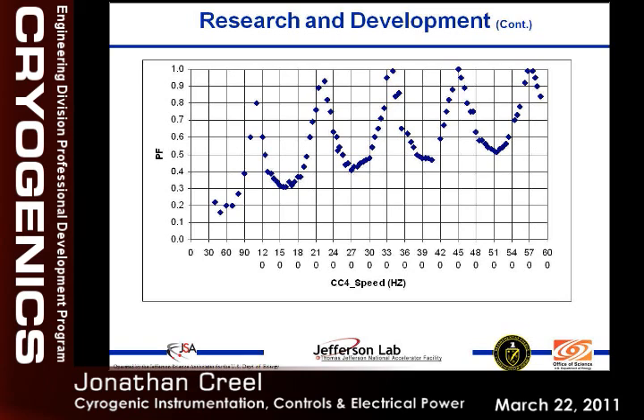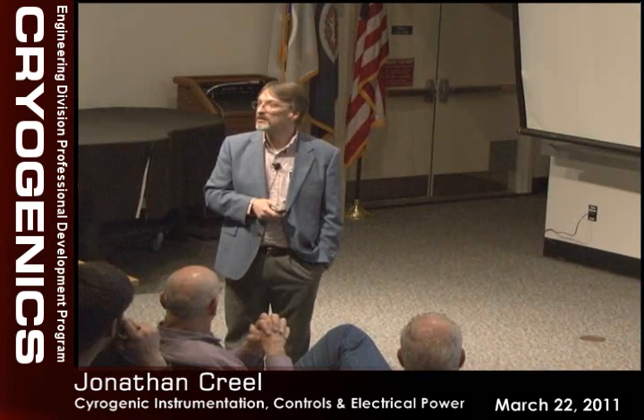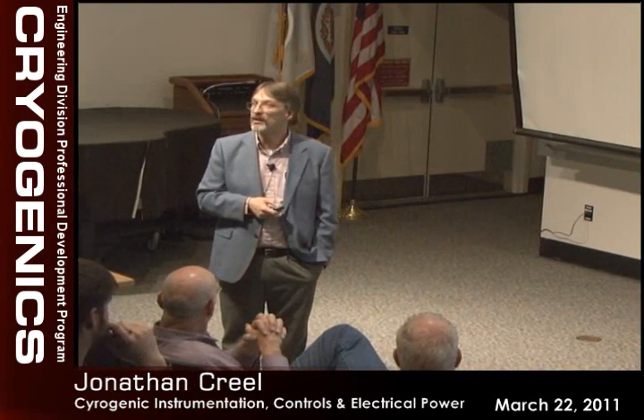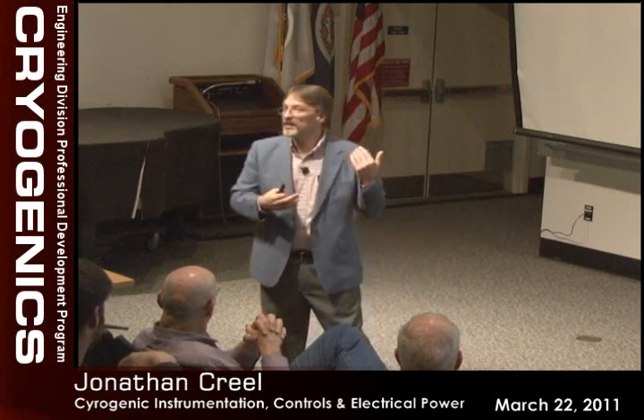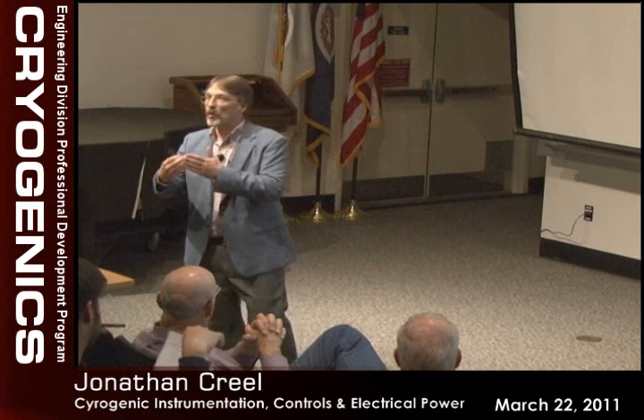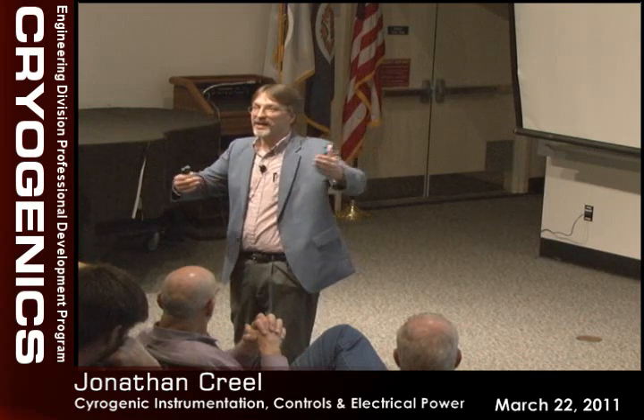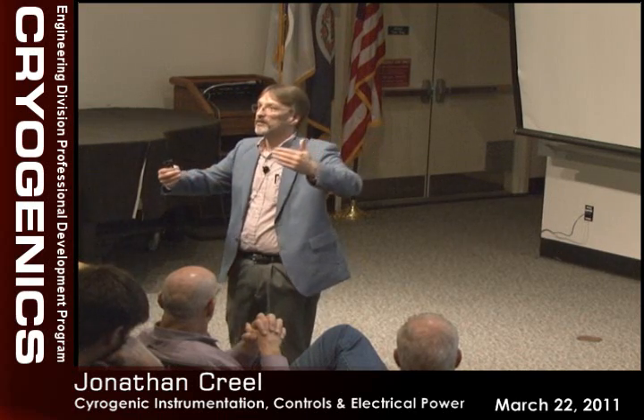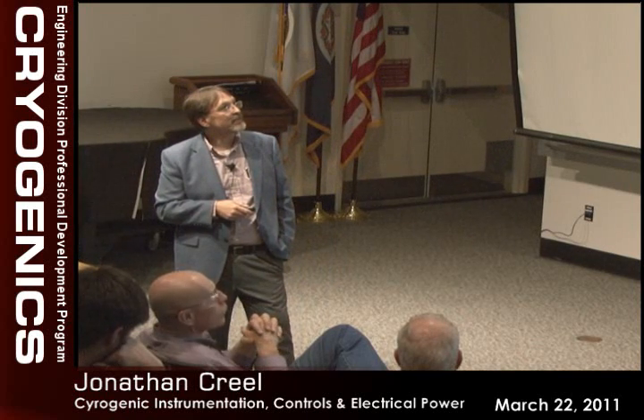And so one of the things that we're really wanting to look into, which we just haven't to this point in time, is why is this? I talked to some people that build these VFDs, and I never could get any real good answers. I don't think they ever really looked at this, at least at the time that I was talking to them on the phone, because in most applications you're not using the VFDs the way we do on the cold compressors, where you've got multiple rotating devices that are all chained together and operating as kind of like one unit.